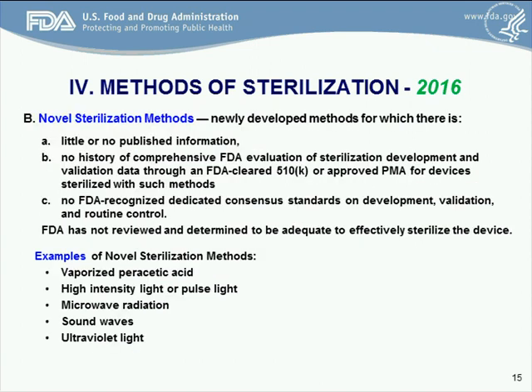The third category is novel sterilization methods. These are newly developed methods for which there is little or no published information, no history of comprehensive FDA evaluation of sterilization development and validation data through an FDA clearance or PMA approval, and no FDA recognized dedicated consensus standards on development, validation, and routine control. Examples of these include vaporized peracetic acid, high-intensity light or pulse light, microwave radiation, sound waves, and ultraviolet light.